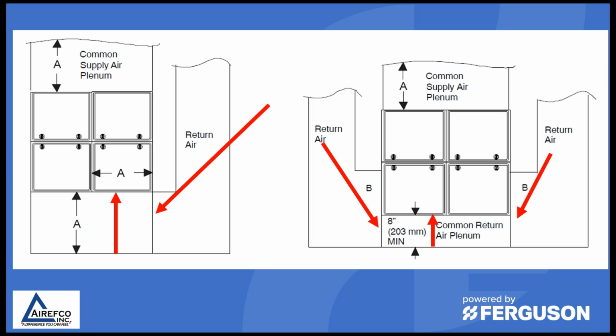Make sure that you refer to the manufacturer's specifications for airflow and for duct design to the furnaces. They, of course, will have a common supply air plenum, and make sure that you meet all the requirements for the distances and measurements that the manufacturer requires.